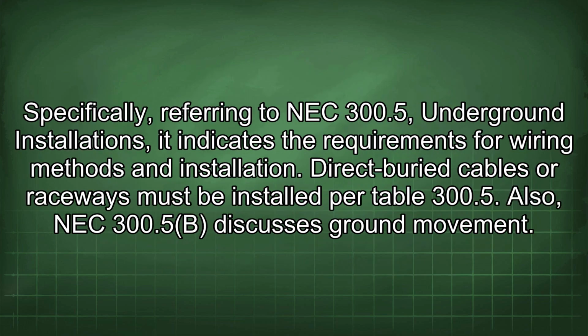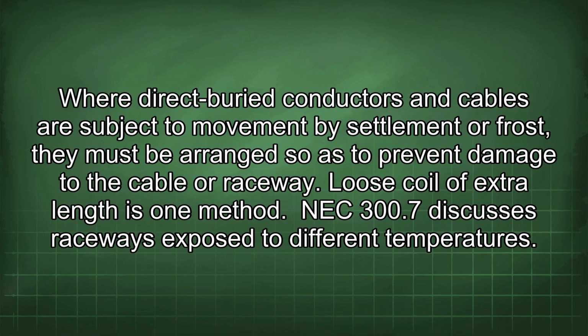Specifically, referring to NEC 300.5, underground installations, it indicates the requirements for wiring methods and installation. Direct buried cables or raceways must be installed per Table 300.5. Also, NEC 300.5(B) discusses ground movement. Where direct buried conductors and cables are subject to movement by settlement or frost, they must be arranged so as to prevent damage to the cable or raceway. A loose coil of extra length is one method.